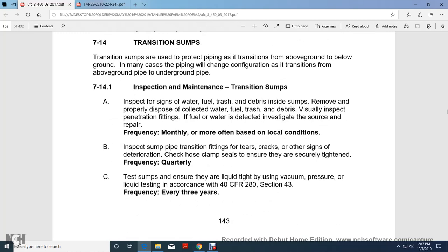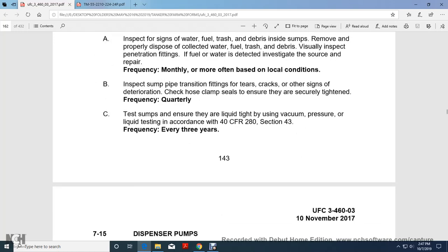In many cases, the piping will change configuration, transitioning from above ground to underground pipe. Inspection maintenance of transition sumps. Inspect for signs of water, fuel, trash, and debris inside the sump. Remove and properly dispose of collected water, fuel, trash, and debris. Visually inspect penetration fittings, and if fuel or water is detected, investigate the source and repair, monthly or more often based on local conditions.